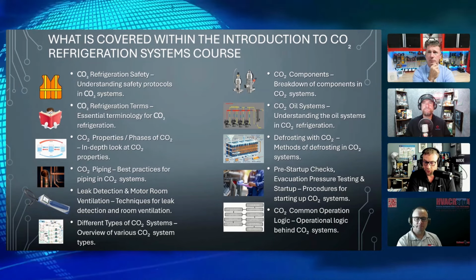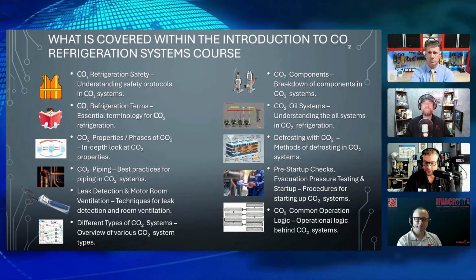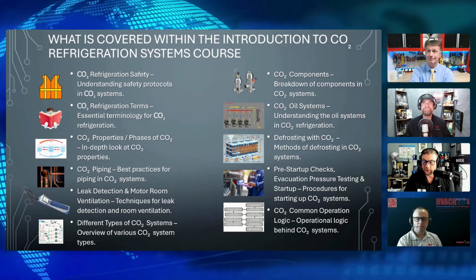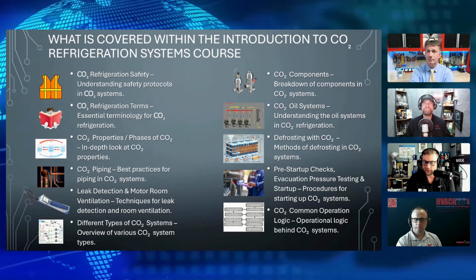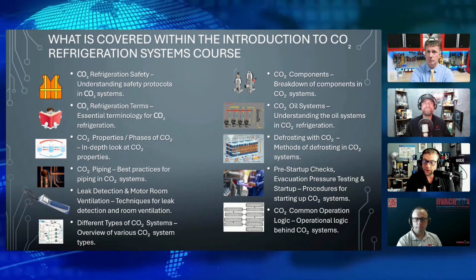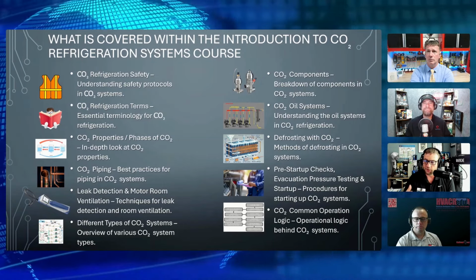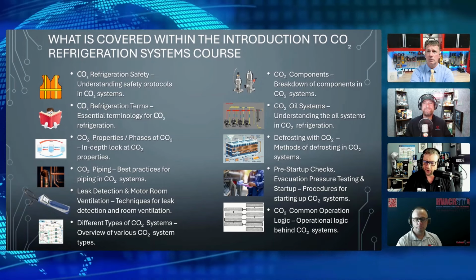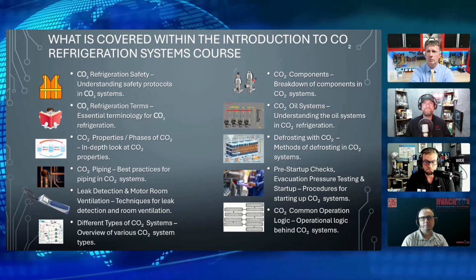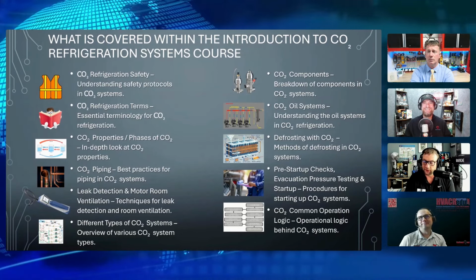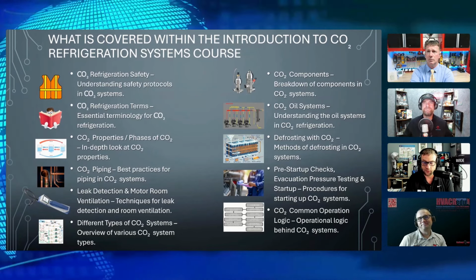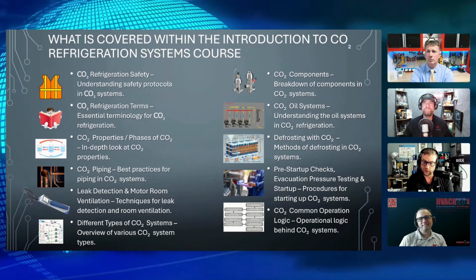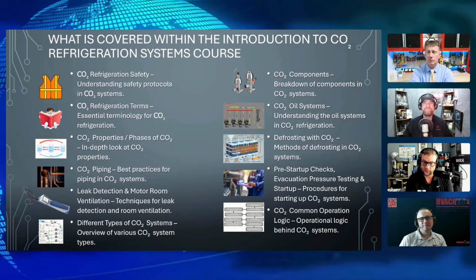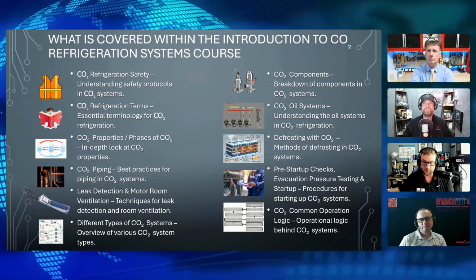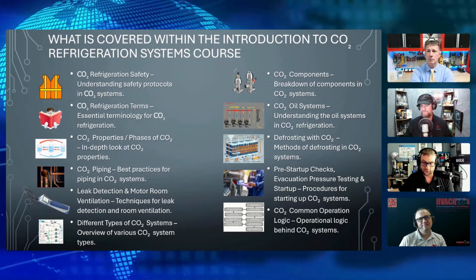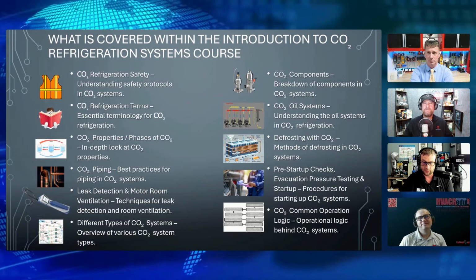Sure. Pre-startup checks, evacuation, and leak checking. There are reliefs all over this thing, which we'll see in the component section. Because of that, it's not like you just fill it up with 400 pounds and the whole system is fine. No, because we have the high side of the system, where they have a relief that, on a transcritical system, could be as high as 1,740 pounds. But on the low temp suction, the relief could be as high as 435. So what do you do?